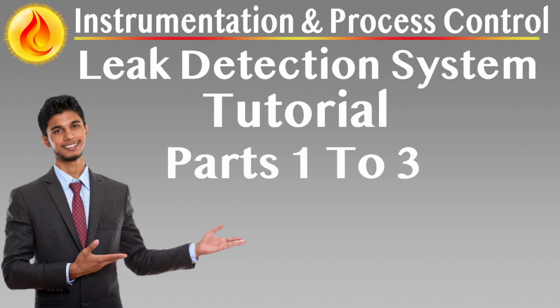Robustness is the LDS's resilience to changing conditions and data quality issues. A robust system continues to operate reliably during power outages, signal dropouts, or transient process events. It must also tolerate fluctuations in product composition, temperature, or flow without misinterpreting them as leaks. The distinction between reliability and robustness is crucial. Reliability pertains to performance under ideal conditions, while robustness measures the system's adaptability to real-world variability and imperfections.